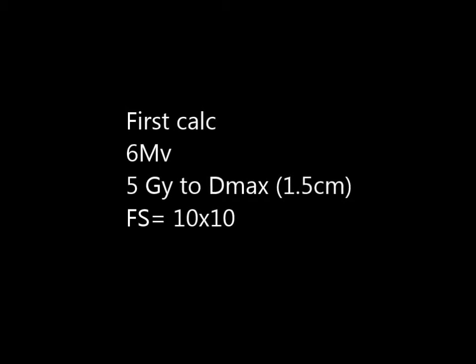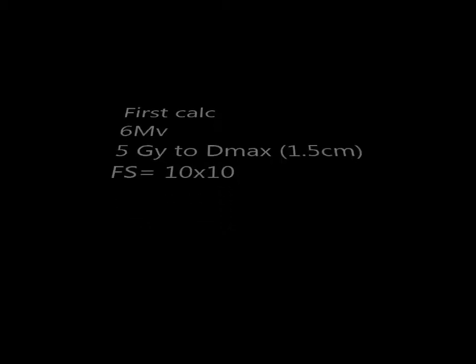We'll start with a very basic example: 6MV, 5Gy to Dmax at 1.5cm, with a field size of 10x10.